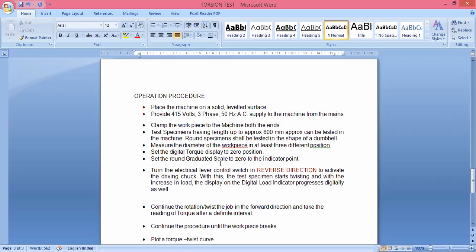There is the indicator point, and you have to rotate the graduated scale by hand so that it reaches the indicator point at the zero value. Now the electrical lever control switch should be turned in the reverse direction to activate the drive. With this, the test specimen starts to twist. With the increase in load, the display of the digital device progresses as well. Here, we run the machine in the reverse direction, not the forward direction, and rotate by holding the grip between the brace. We start twisting the specimen quickly.